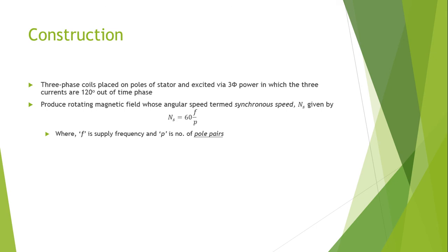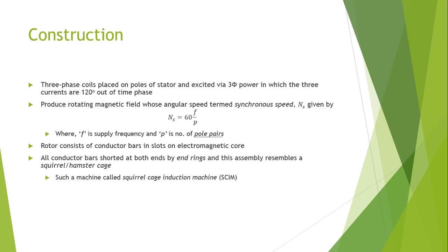p is the number of pole pairs. The rotor consists of conductor bars in slots on an electromagnetic core. All conductor bars are shorted at both ends by end rings, and this assembly resembles a squirrel cage. Such a machine is known as a squirrel cage induction machine.